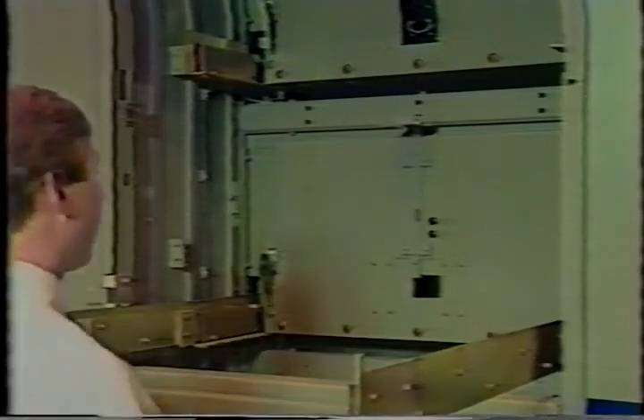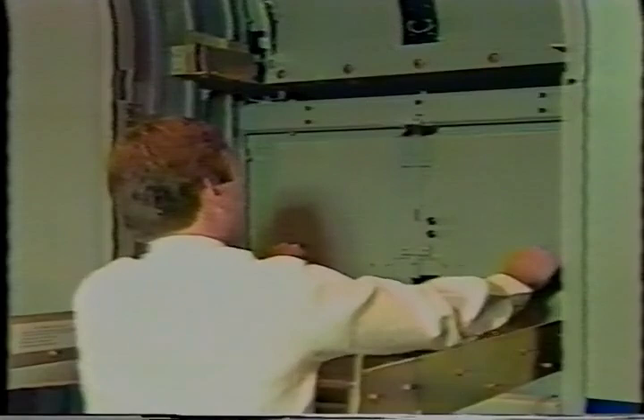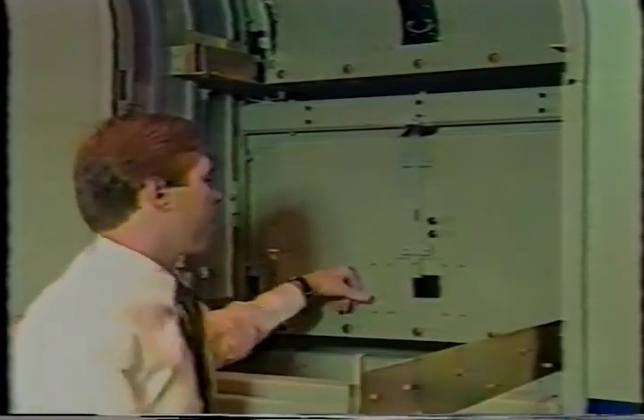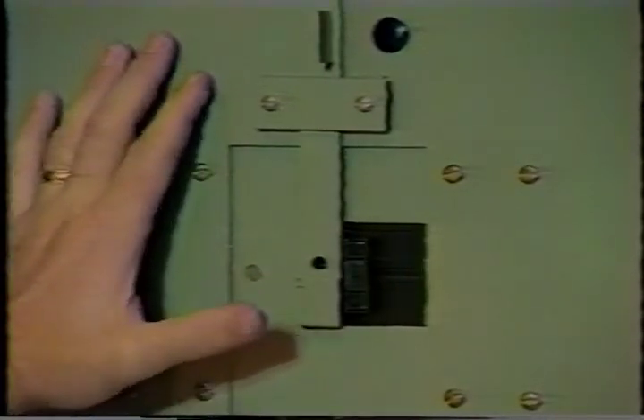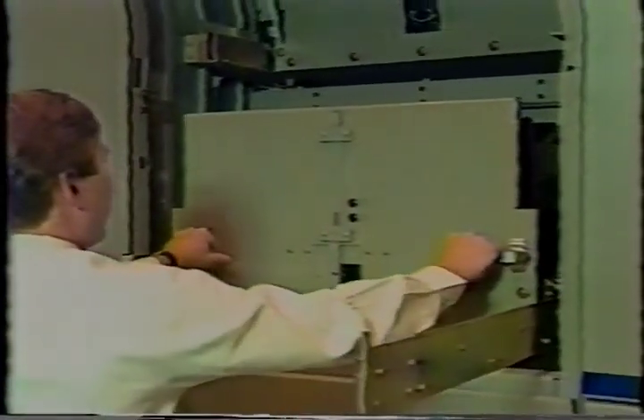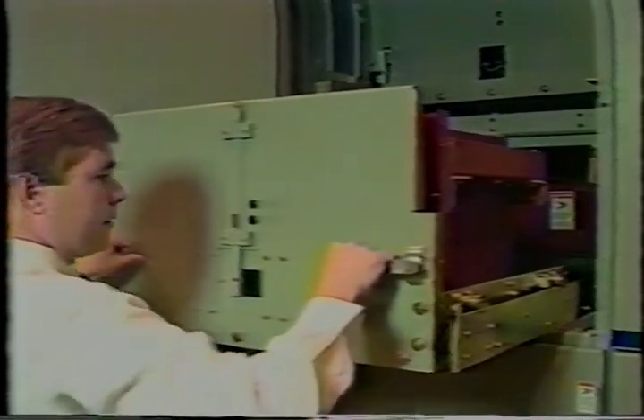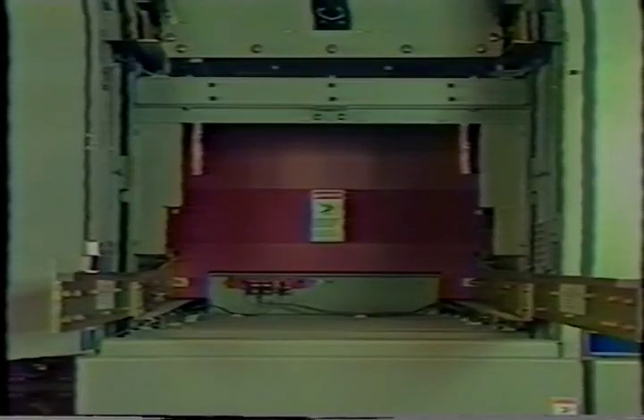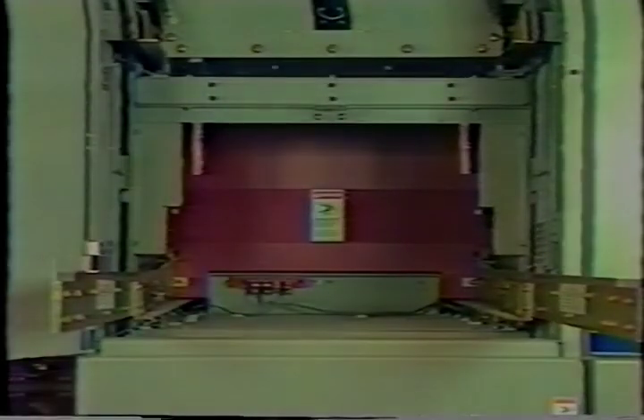This switchgear can be provided with drawer-mounted voltage and control power transformers. They are connected and disconnected via extension rails identical to those provided for the circuit breakers. A built-in interlock provided on a control power transformer drawer requires the operator to trip the main secondary breaker before the drawer can be disconnected. Withdrawing the drawers automatically disconnects both the primary and secondary terminals. The primary fuses are also momentarily grounded to assure the operator the transformers are de-energized. In VacCLAD W switchgear, simply opening the drawer operates shutters which automatically cover the primary disconnects.